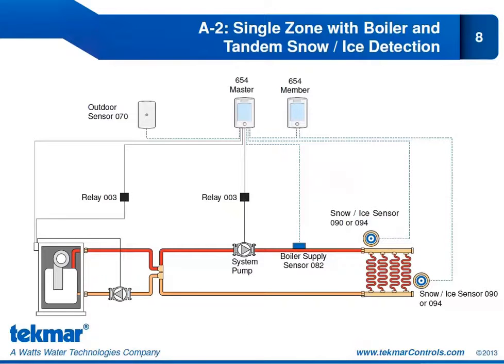Application 2 shows a single zone where we're operating the boiler and we are doing tandem snow ice detection. Now we will talk about the tandem snow ice detection feature at length later in the training presentation. Right now we'll just give you an overview of what this is. We have a single snowmelt zone, and in this single zone we are going to install 2 snow ice sensors, 090 or 094. Now reasons we might want to do that would be if it is a particularly large snowmelt zone. So imagine an extremely long driveway where perhaps one snow ice sensor isn't representative of the entire snowmelt area. We can also choose to do this if we want to have some redundancy. So we want a fail-safe. In case one of those sensors should fail, we want to have some backup operation. And if you are desiring operation such as that, then the tandem snow ice detection would be for you.